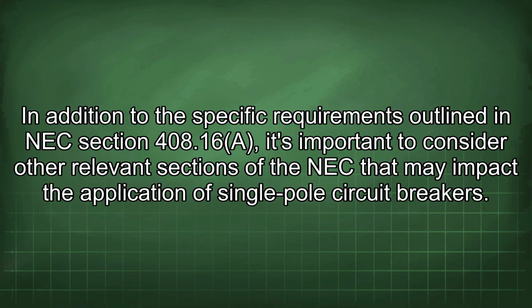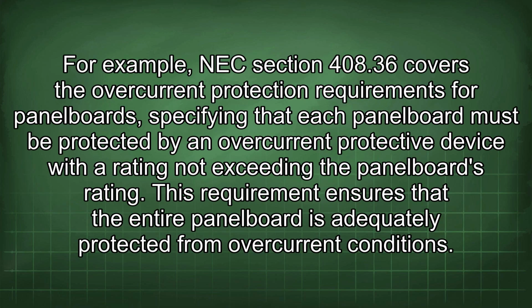In addition to the specific requirements outlined in NEC Section 408.16(A), it's important to consider other relevant sections of the NEC that may impact the application of single-pole circuit breakers. For example, NEC Section 408.36 covers the overcurrent protection requirements for panel boards, specifying that each panel board must be protected by an overcurrent protective device with a rating not exceeding the panel board's rating. This requirement ensures that the entire panel board is adequately protected from overcurrent conditions.